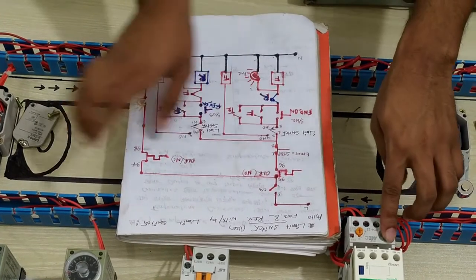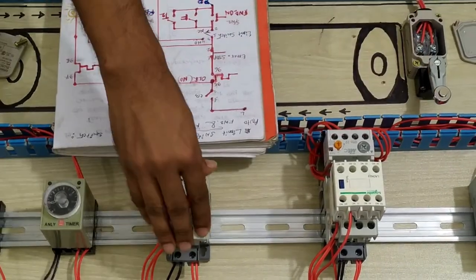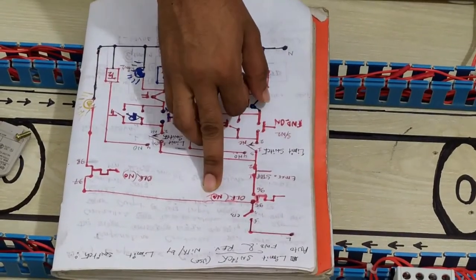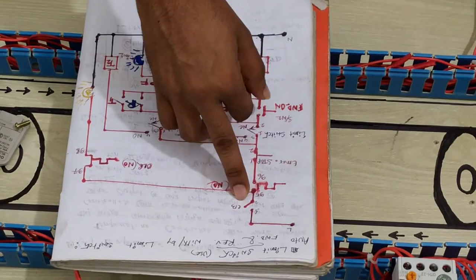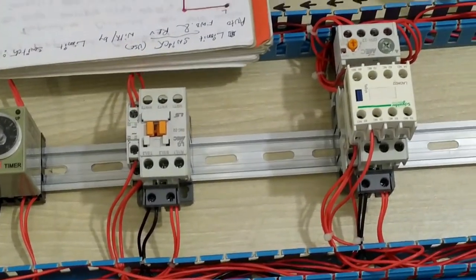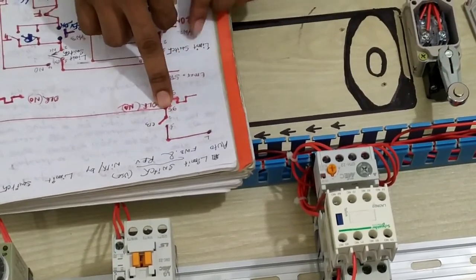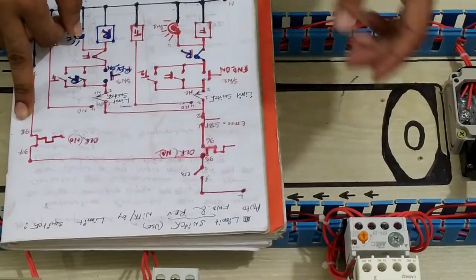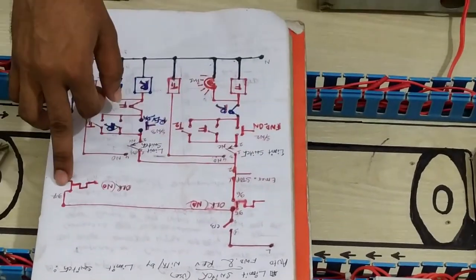These two terminals are directly connected to pin 95 of the overload. This overload is connected to your forward magnetic contactor and your reverse magnetic contactor. Pins 95 and 96 of the overload are normally closed (NC). That means when power is supplied, it is directly connected — phase only — to pin 95 of the overload, with pin 96 as the outgoing. Pin 95 is also directly connected to pin 97.